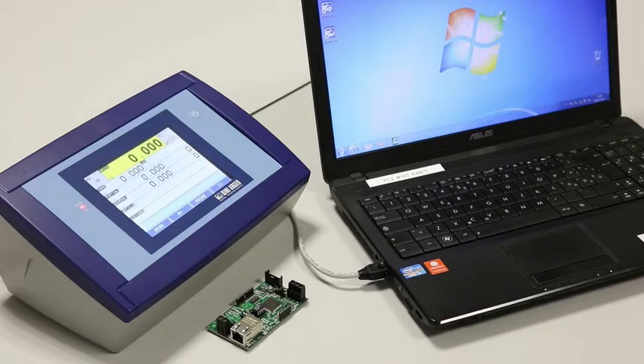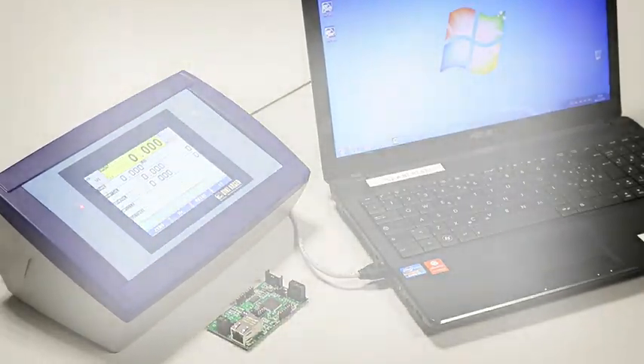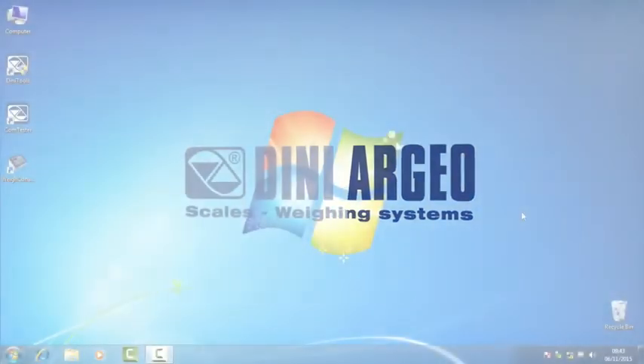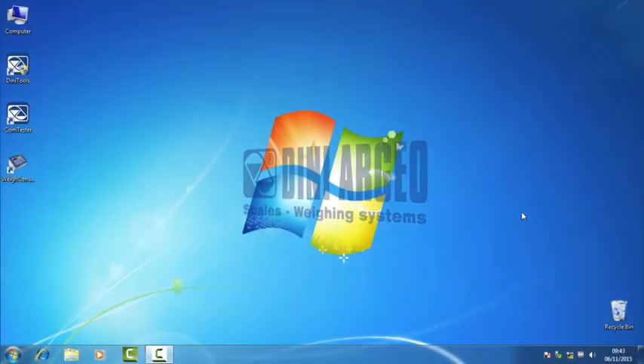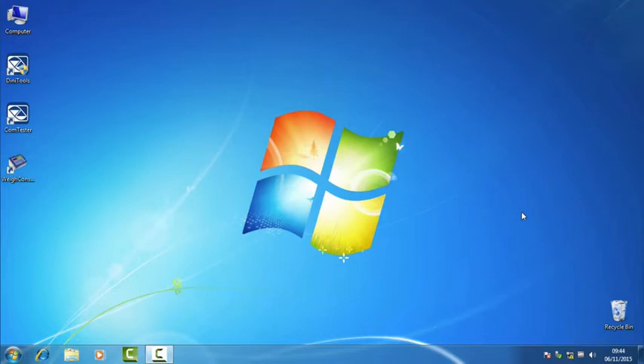Ok, we are ready to start. First of all, we need to create a simple network between the laptop and the indicator. To do that, we have to set the laptop IP address with the same network as the indicator port, changing the host code. Take note that the indicator factory IP address is always 192.168.16.205 and the subnet mask is 255.255.255.0.